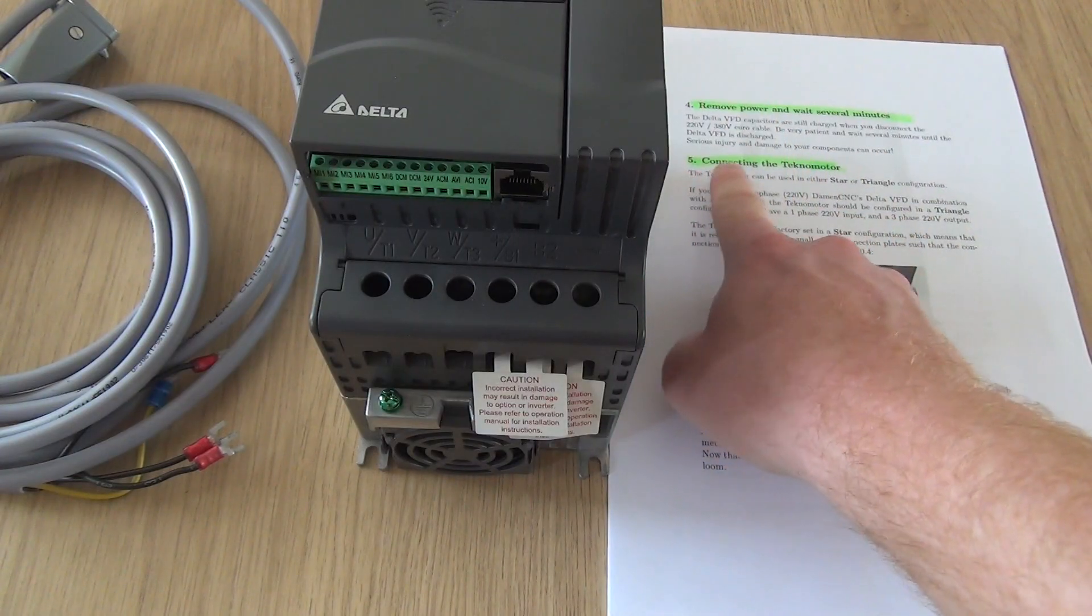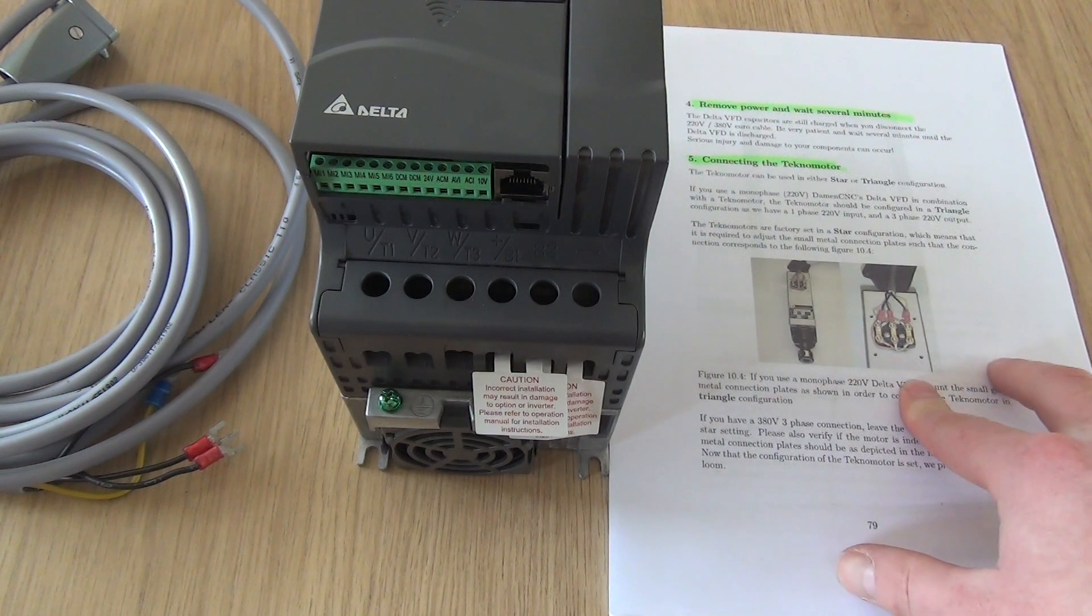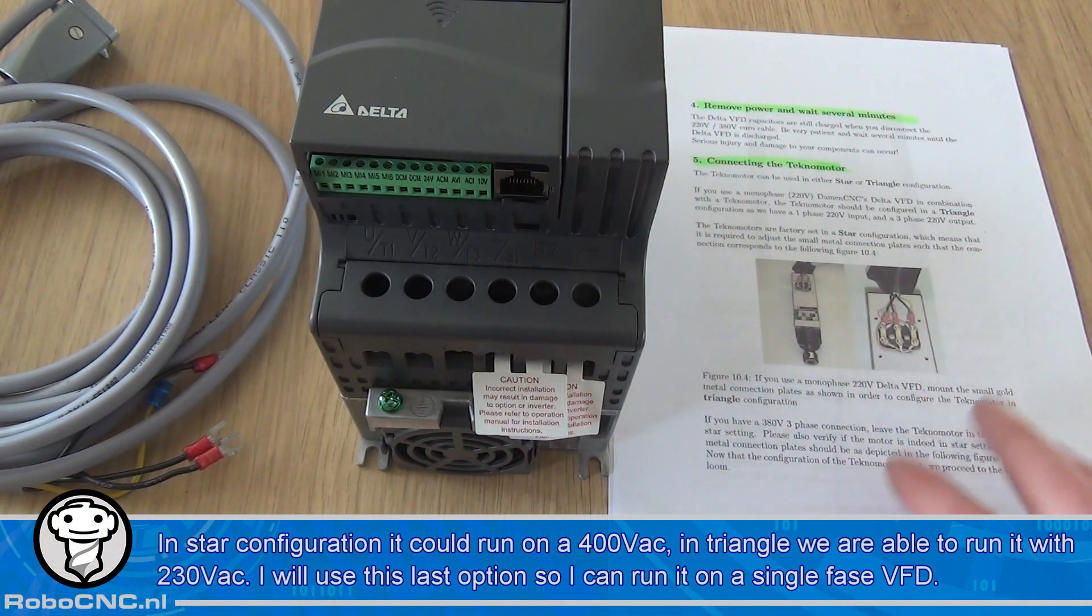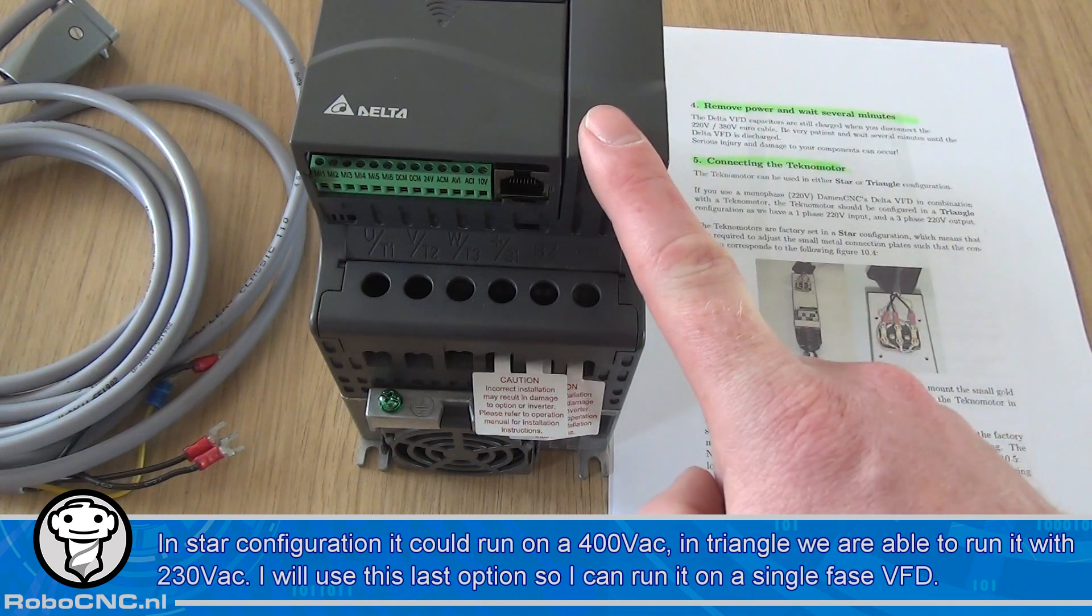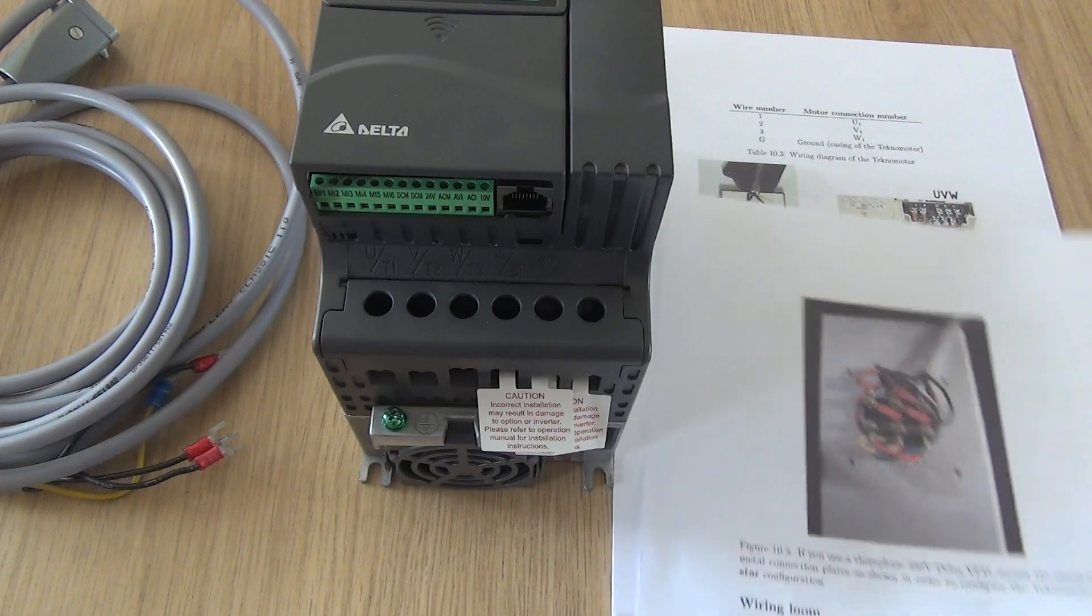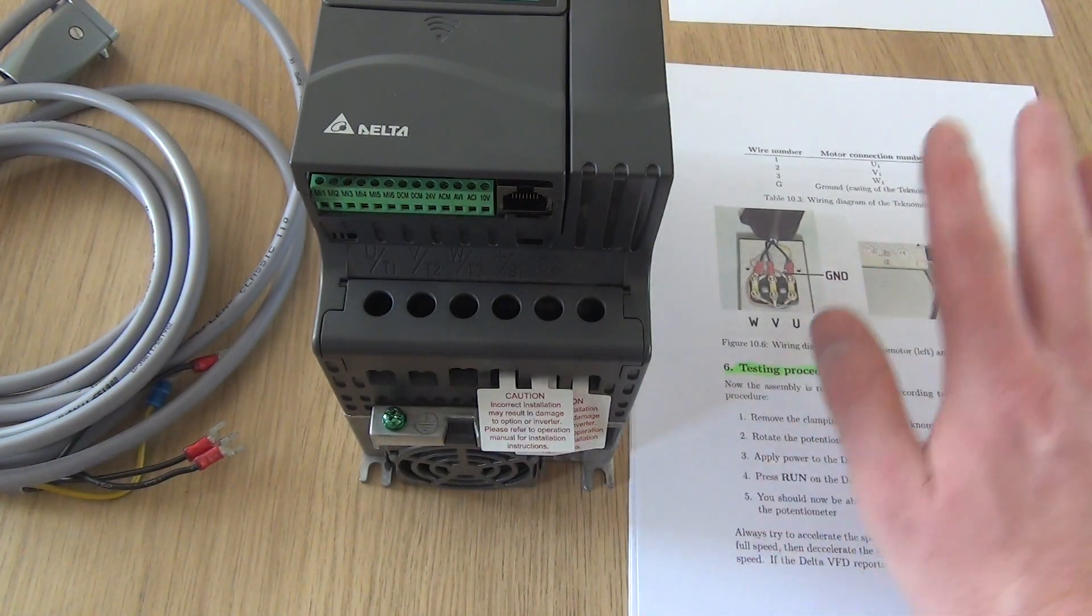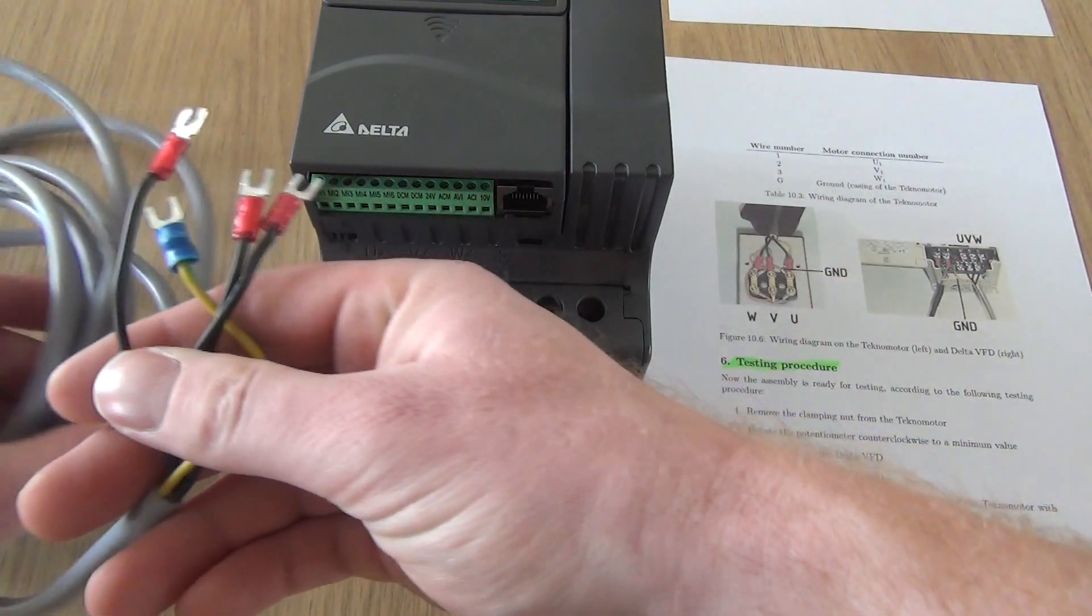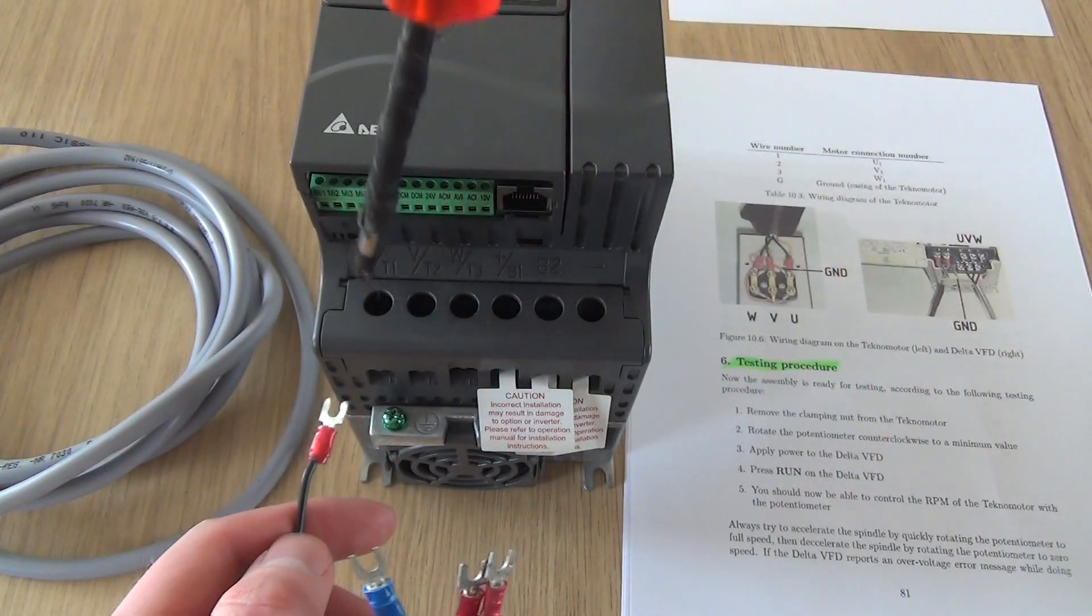So chapter 5, connecting the Teknomotor. I'm not going to do an in-depth review on triangular versus star configuration, nor am I going to give lessons in connecting a motor. There are many on YouTube you can find. But basically, we are using a single phase 230 volt connection. If you're using a single phase unit like this and the Teknomotor, we are in need of the triangle configuration. So make sure your connection box inside the Teknomotor is correctly configured for triangular connection. You can find it all in this appendix. And after which we are going to connect these to the UVW connection.